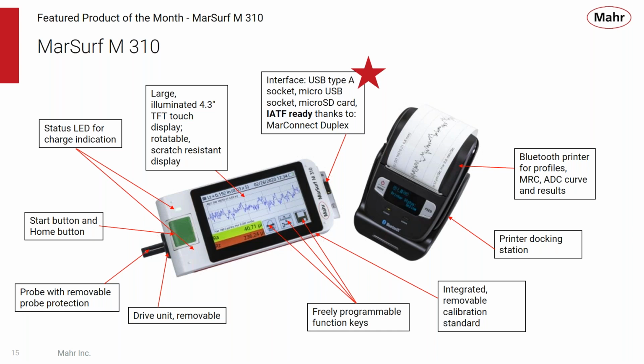We have an integrated removable calibration standard, which is used to ensure that the system is working properly. It's freely programmable, has function keys which you can dedicate to a function for changing tolerances, saving data, or looking at different parameters. It has a removable drive system so that you can remove the drive and fixture it into small areas or sections of parts.